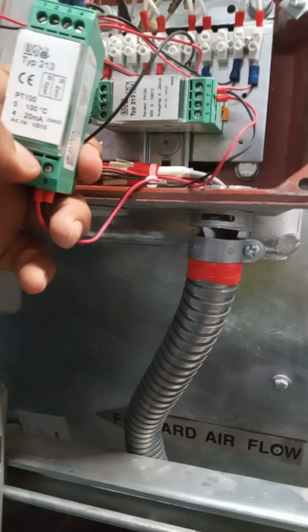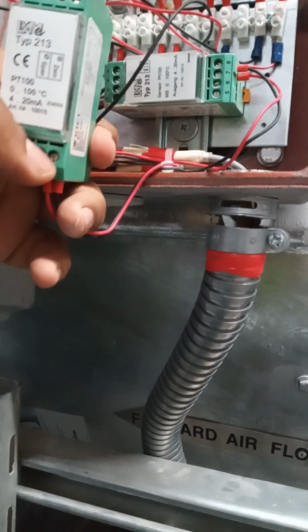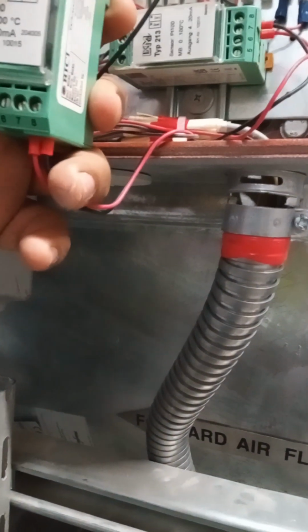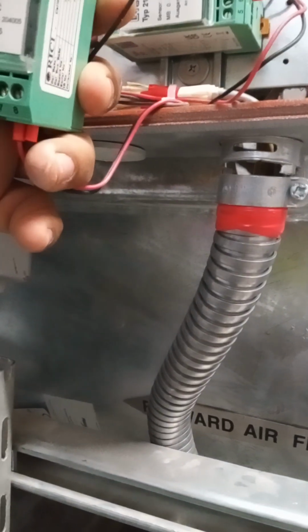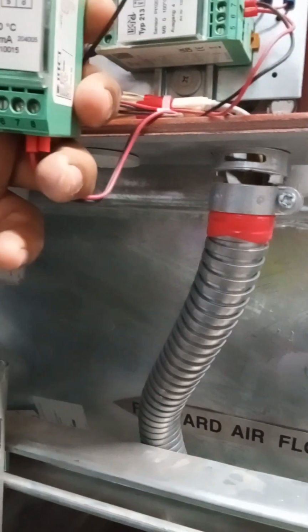So you can measure the 4 to 20 milliamps output here, and otherwise you can check resistance. Here you will get around 120 and above resistance. You can put a multimeter in resistance mode and check. Otherwise you can directly measure. Even when the fan is off, you will get the bearing temperature. You can just measure the resistance here.